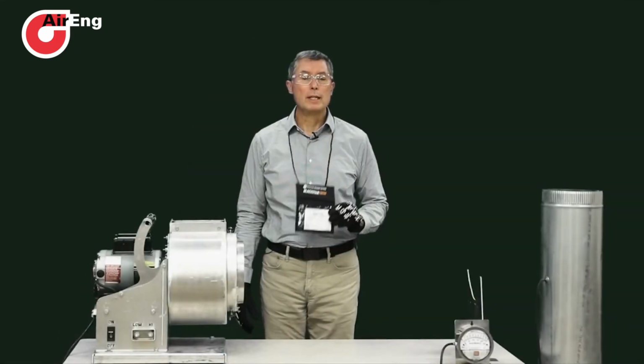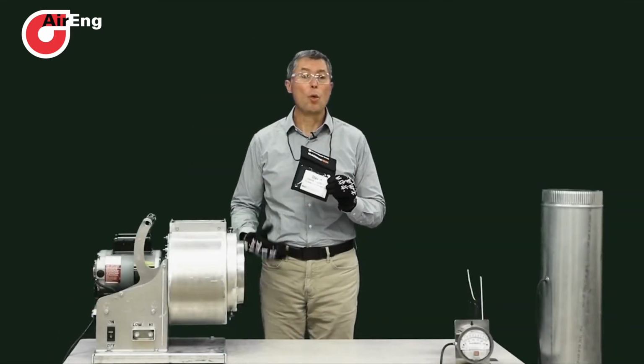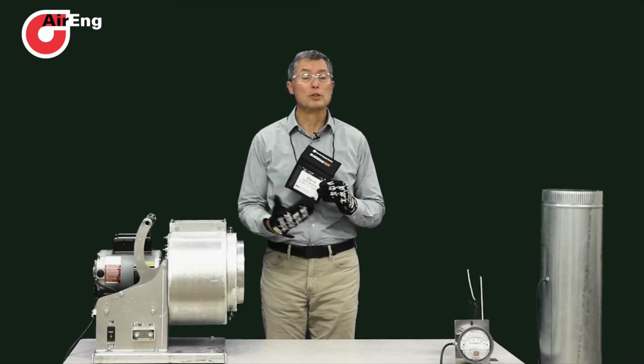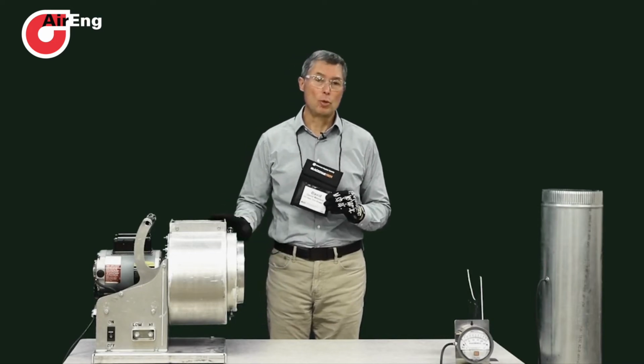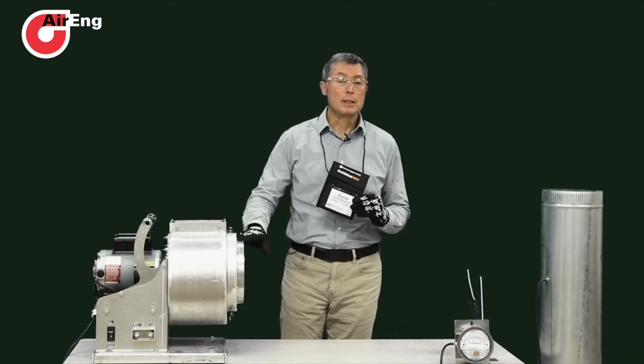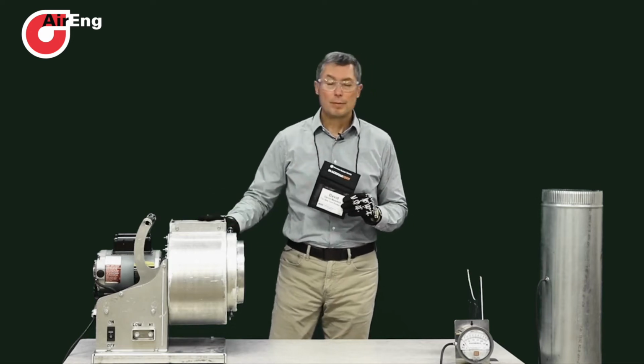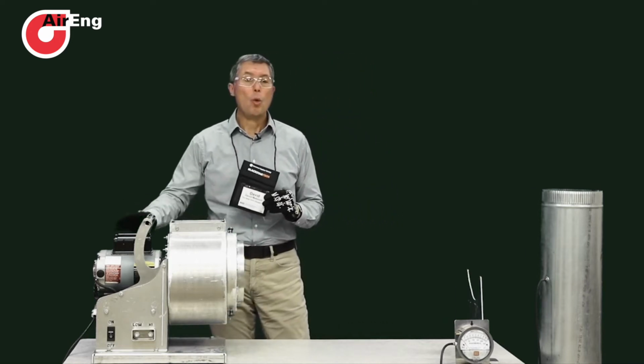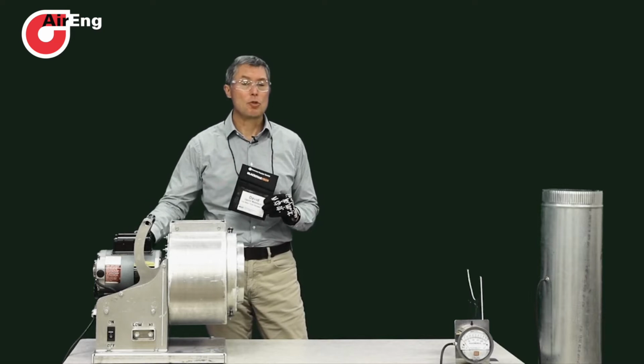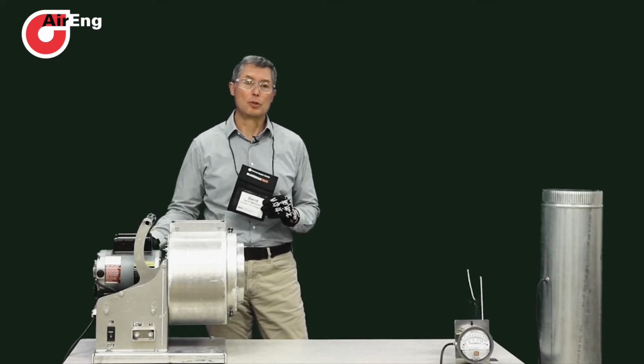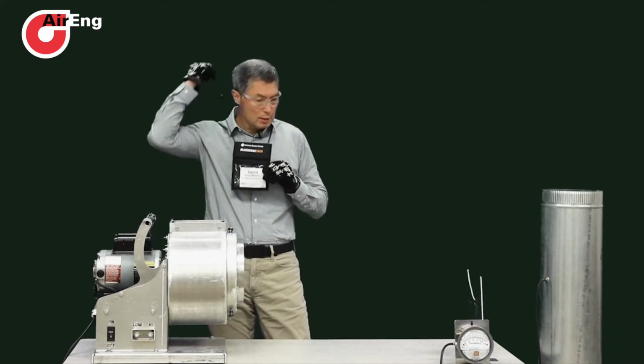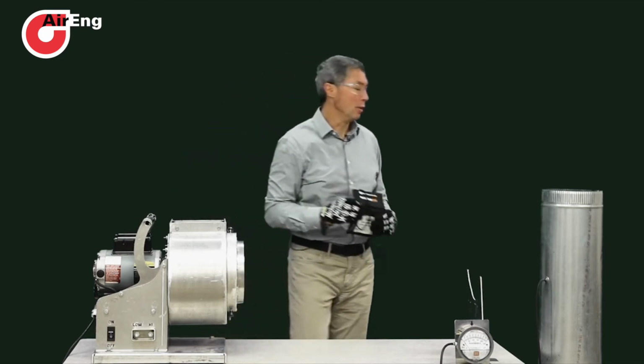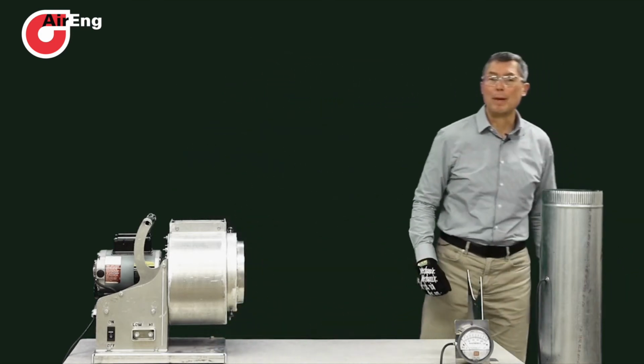What we want to avoid is any loose articles like this lanyard, or loose articles of clothing, rings, watches near a piece of rotating equipment. These items can get sucked into the fan inlet, get lodged into the fan discharge, or, if we have shaft and bearings, V-belt drive or coupling, can get caught up on those devices as well. So the best thing to do is discard these items until after the presentation, and then you can put them back on again.